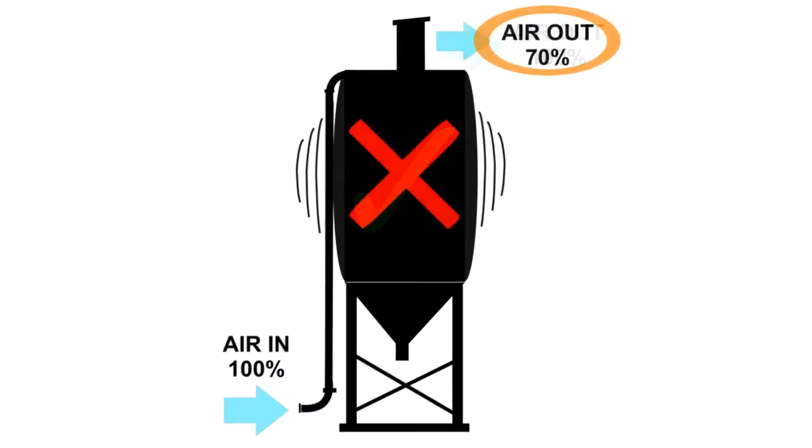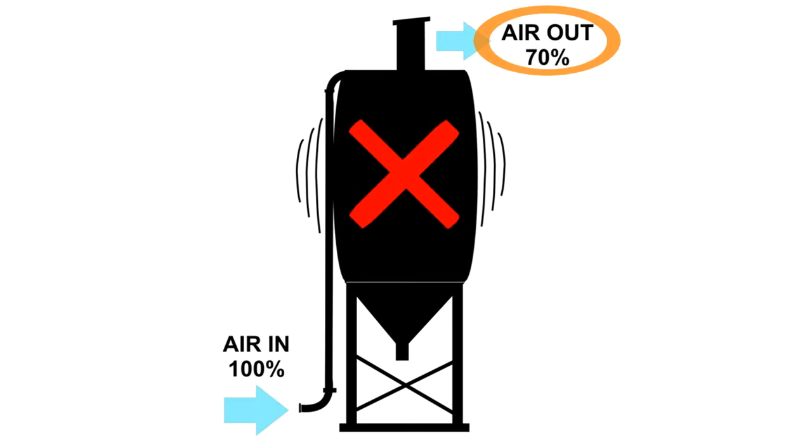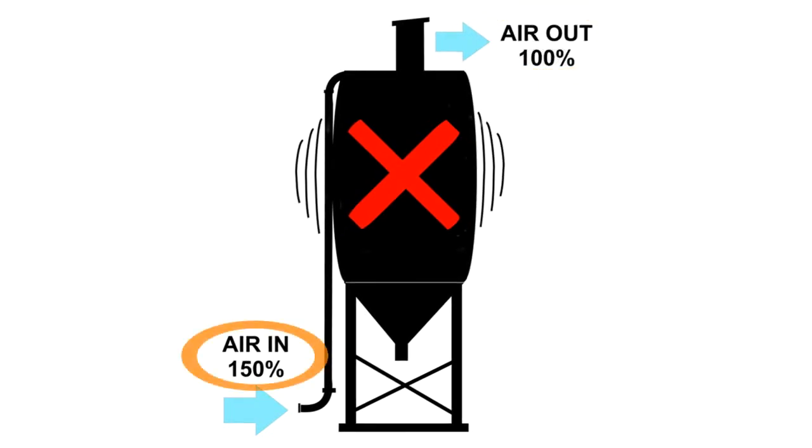However, if the air flow out is restricted, for example by a filter blockage, or if there is too much air coming into the vessel to be safely vented, which is likely a result of uncontrolled tanker discharge, then the silo is at risk of over pressurisation. This happens far too often.